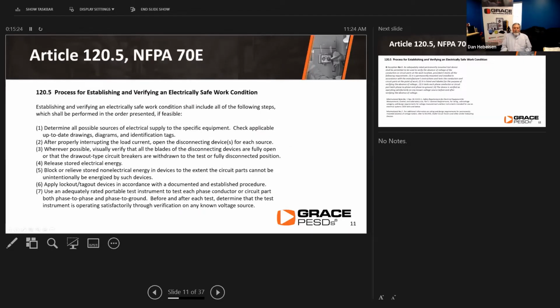That being said, Article 120 of NFPA 70E helps us in creating the environment for and a process for establishing an electrically safe work condition. And the first thing that you're going to want to do is to determine all possible sources of the electrical supply to the specific equipment. You're going to check the applicable up-to-date drawings, diagrams, and identification tags. Now, this is critically important to make sure that you know where it's being supplied from and make sure that your drawings and information is up to date.